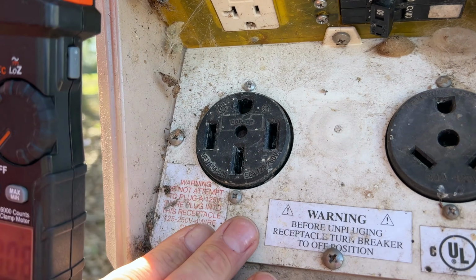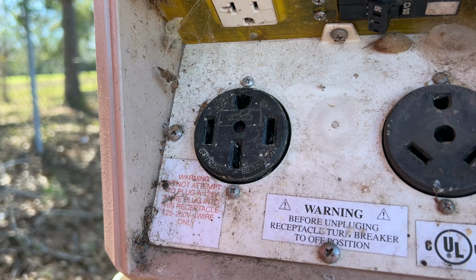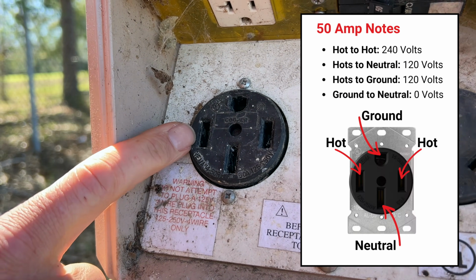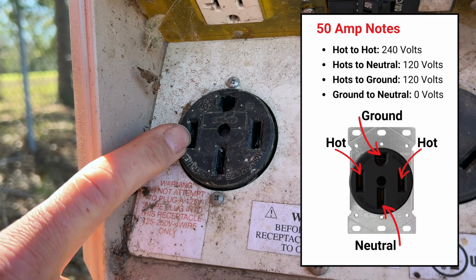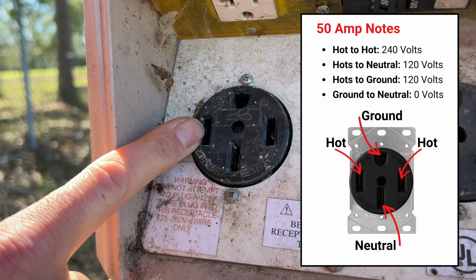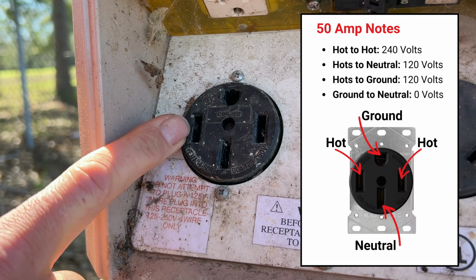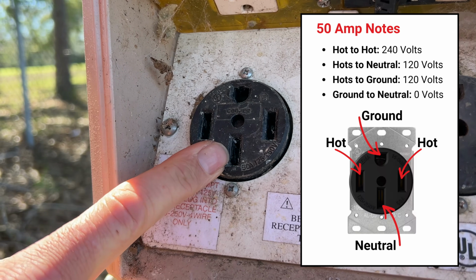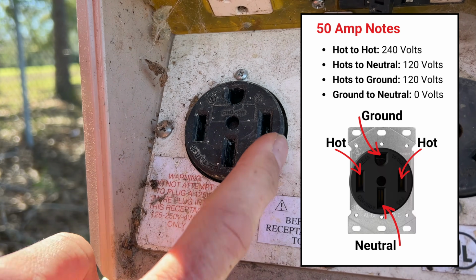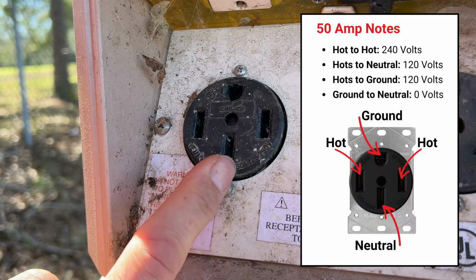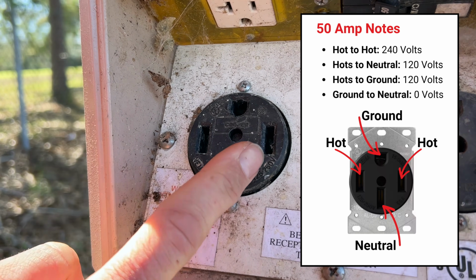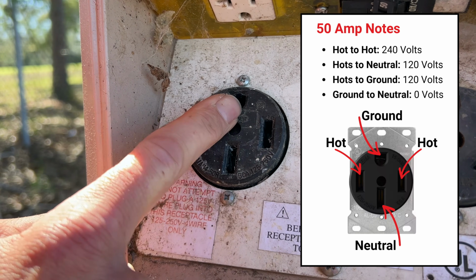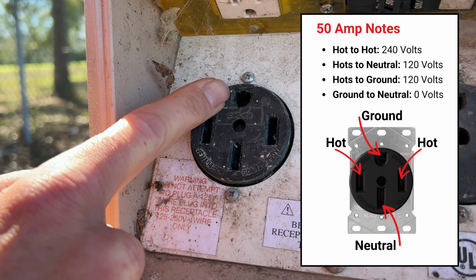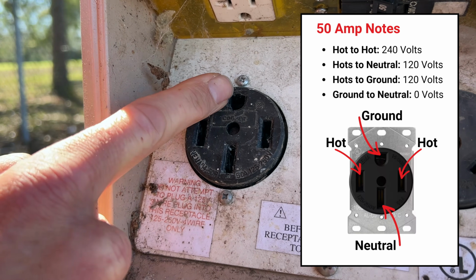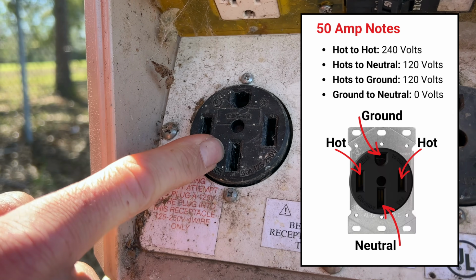Now all of our voltage was correct. I'll get this out of the way so I can point. Now we had 240 volts between our two hot legs, so the right and left was 240. Between our hot and neutrals, so hot on the left to neutral here was 120. Our hot on the right to neutral here was 120. And with our ground, between hot to ground was 120. And the other hot to ground was 120. And then our ground to neutral is 0.